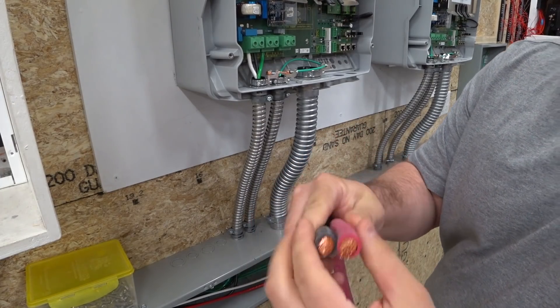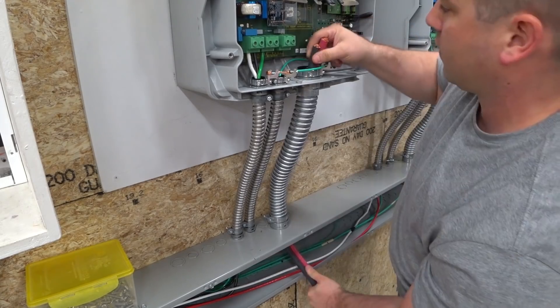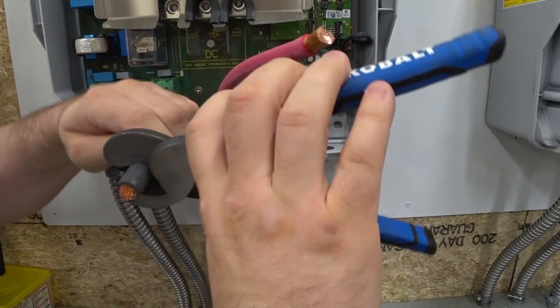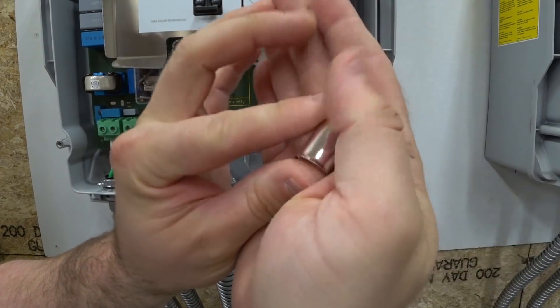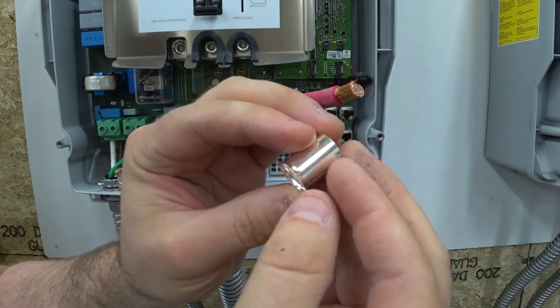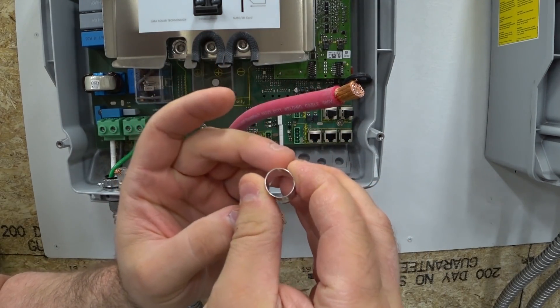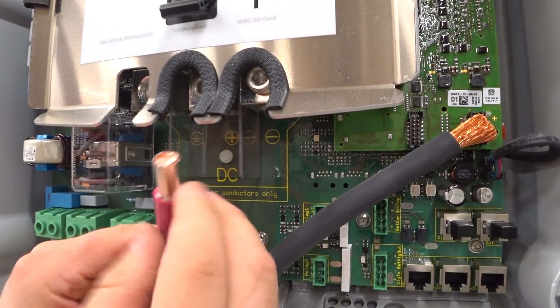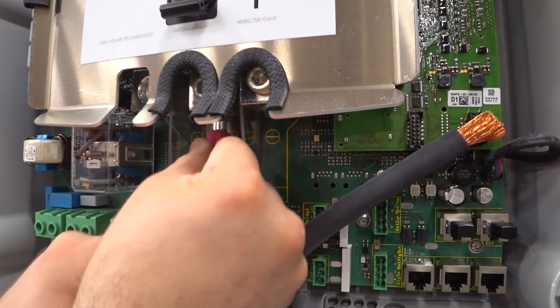Here's the 2-0 cable, and we'll just feed both up through here — both the positive and negative. Here's the ferrule. You can see it's rather big, and it's kind of funnel-shaped on one side and square on the other. It's very, very thin, so I could bend this with my fingers. There's the ferrule on the end of the wire, and it's containing all of the strands. Now I'll just get it up in there.